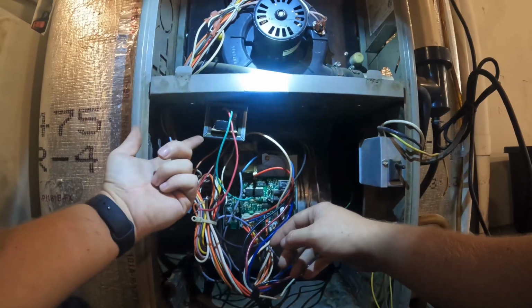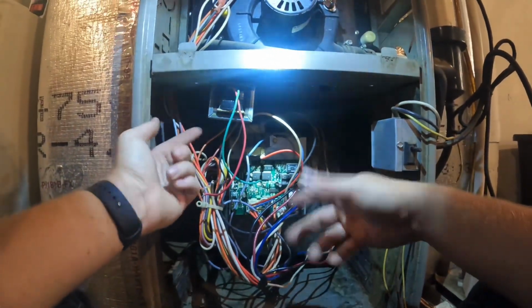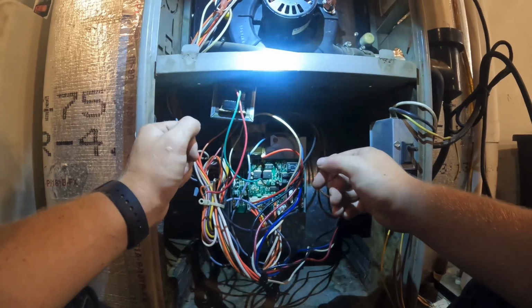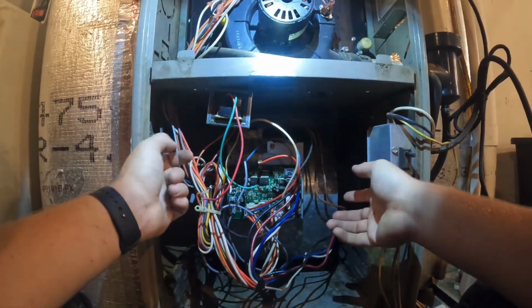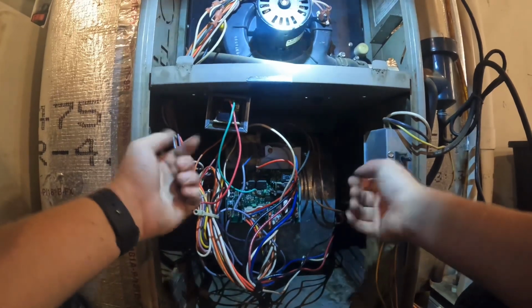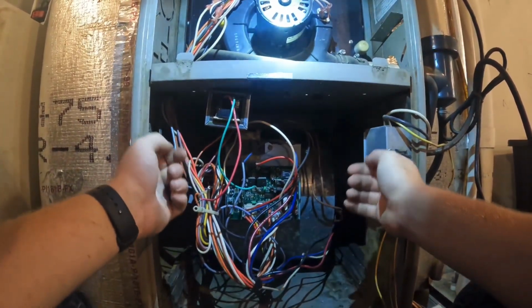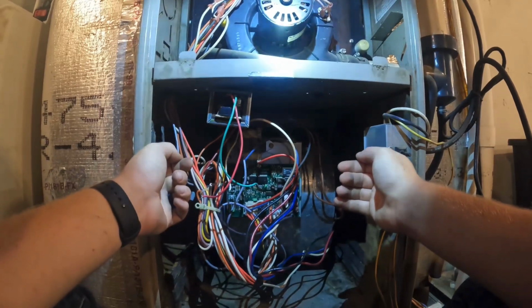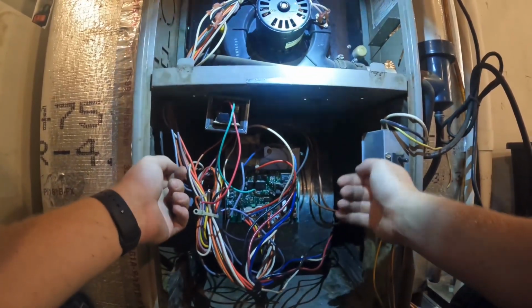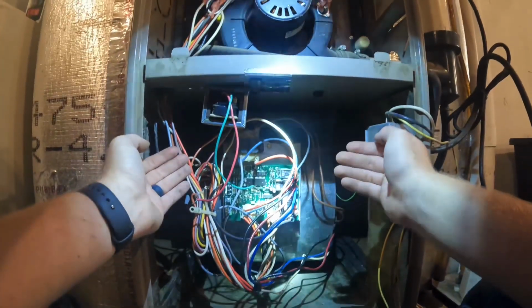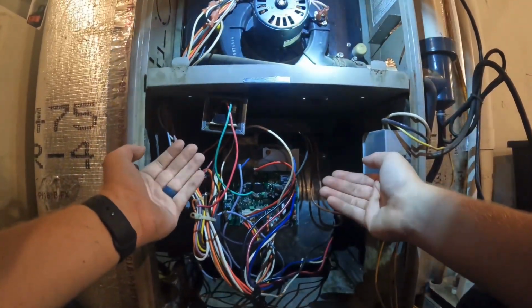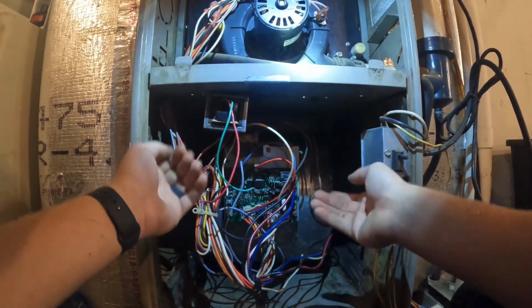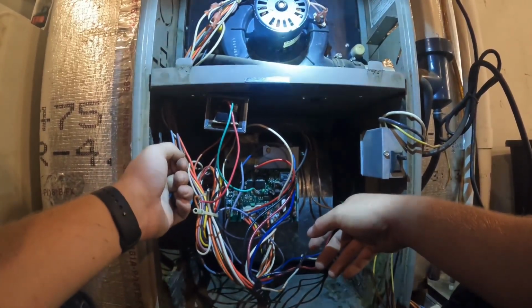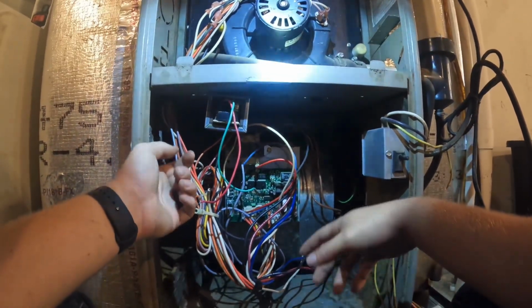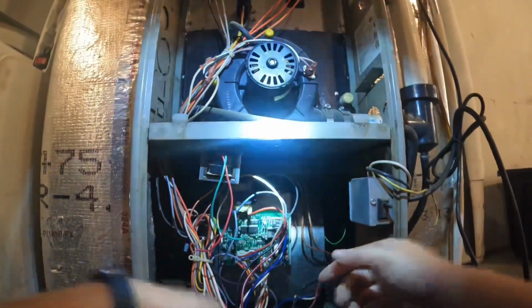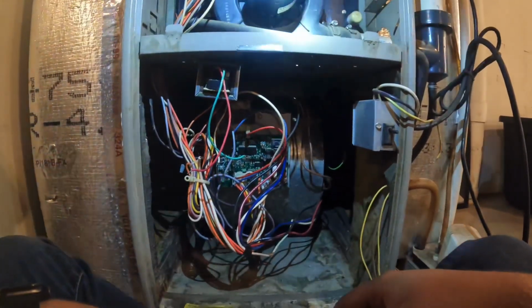Got my transformer mounted back for the zone board. For most of y'all that's not aware, a zone board, depending on the brand, most all of them, cannot run off the system transformer. They have to have an independent transformer just for the zone board. If not, there are times it can pull the voltage down too low, cause the system to trip out, and cause other problems. So always have an independent transformer if you're running a zone board.